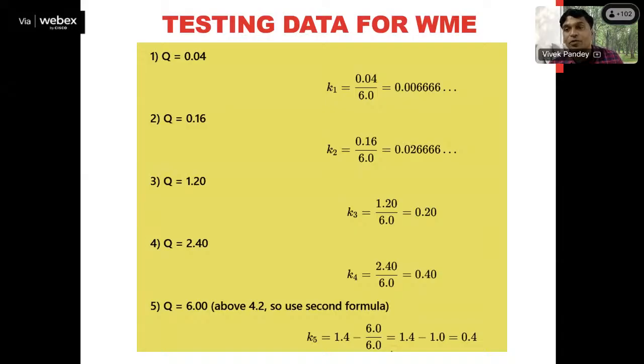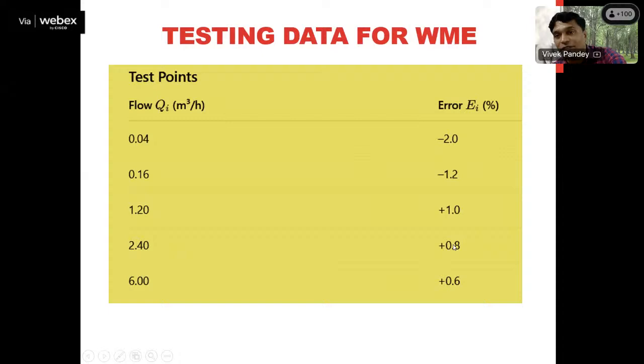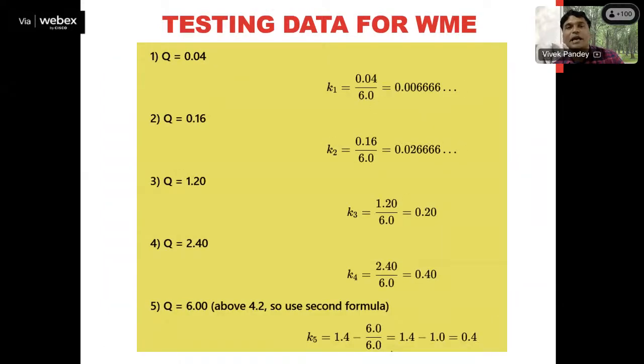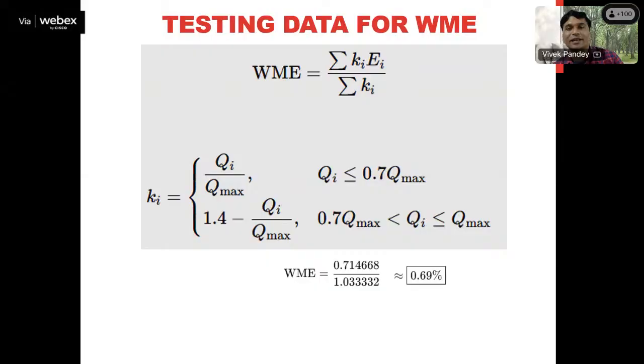And the maximum flow rate is always more than 0.7 times Q maximum. So in that case the formula is changed. K5 is calculated using 1.4 minus Qi upon Q maximum, and here Qi and Q max are the same, so that's why it is coming as 0.4. So we have got the values of K1, K2, K3, K4, K5, and we have got the values of E1, E2, E3, E4, E5. Now we can simply apply them in this formula. You can see here.